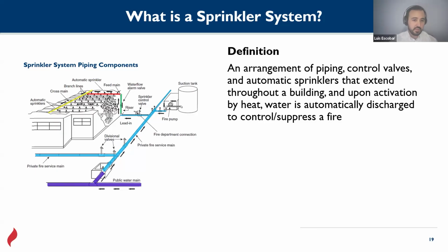But let's go back to the definition. So this is a typical fire sprinkler underground arrangement. Could be a water storage tank, fire pump, underground piping, then control valves as we saw here, riser, where most of the time we have the valves to control the system to close and test and for maintenance purposes. Piping, obviously, we have feed mains, cross mains, and branch lines, and these automatic sprinklers by themselves. So all this is considered a fire sprinkler system that is going to prevent fires in building constructions.